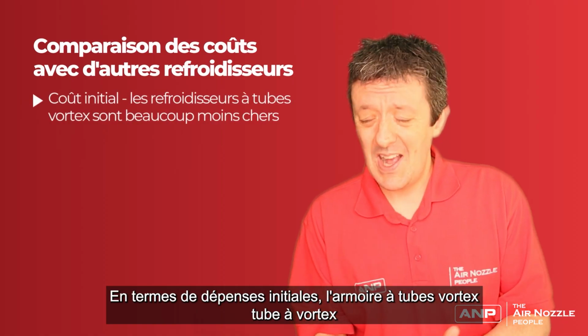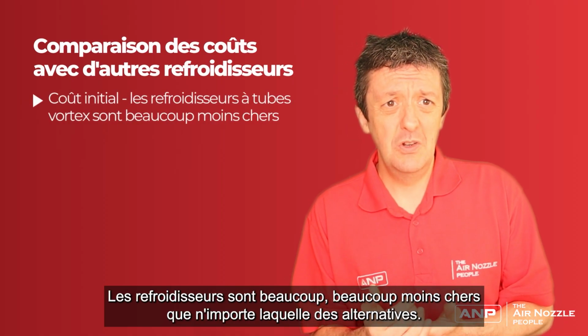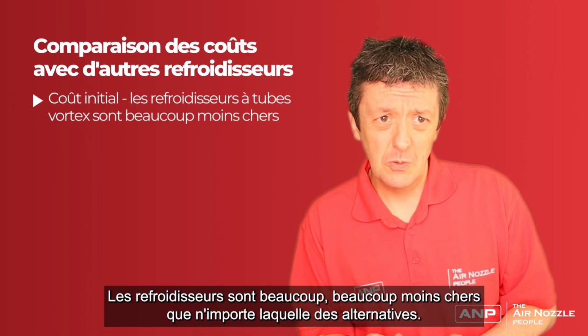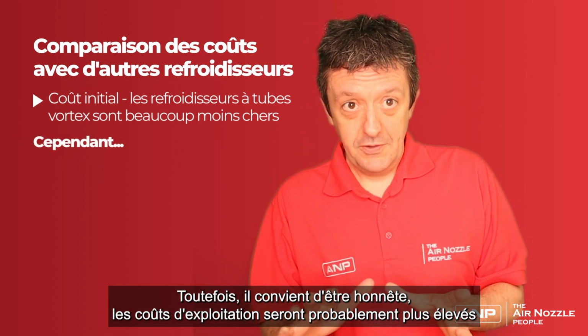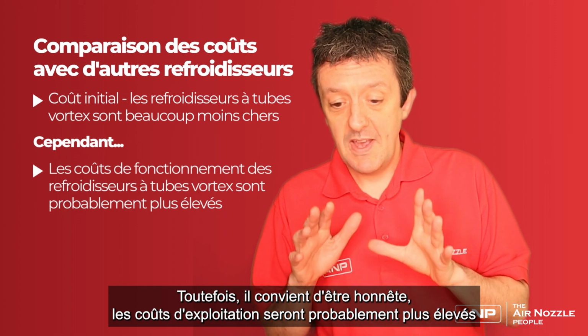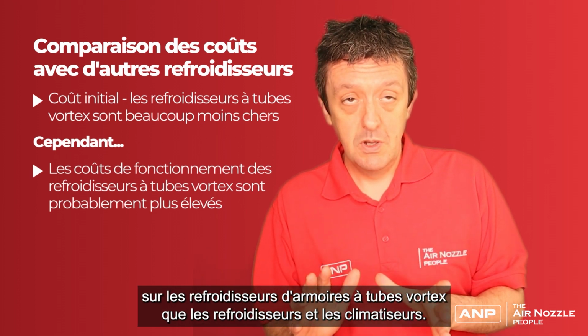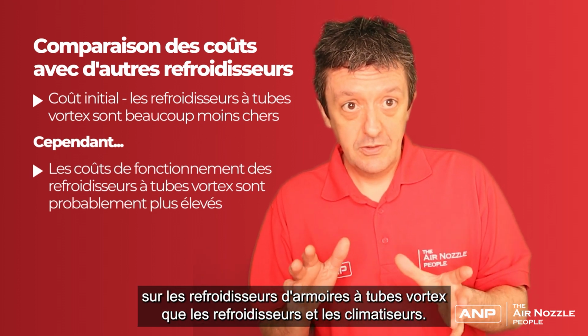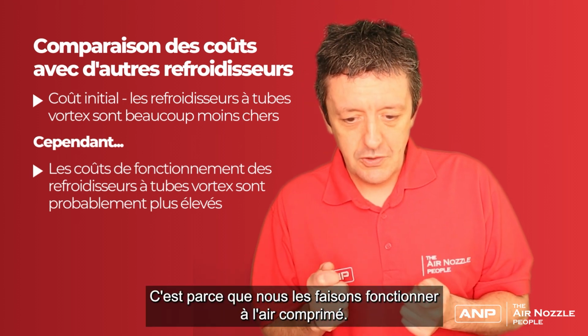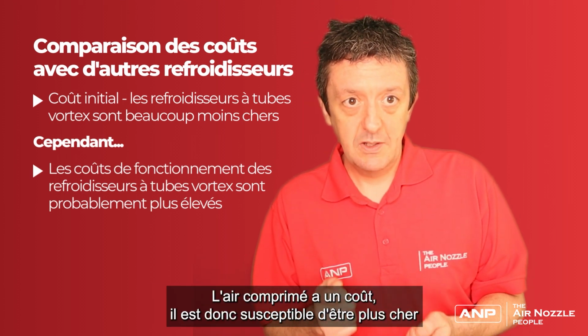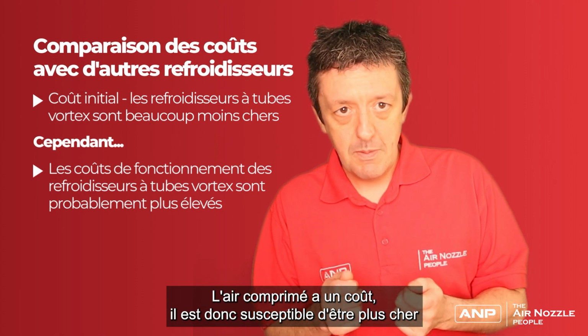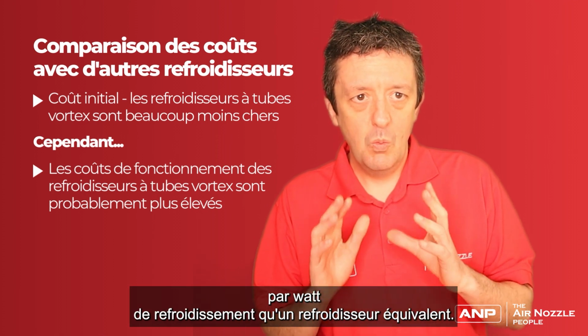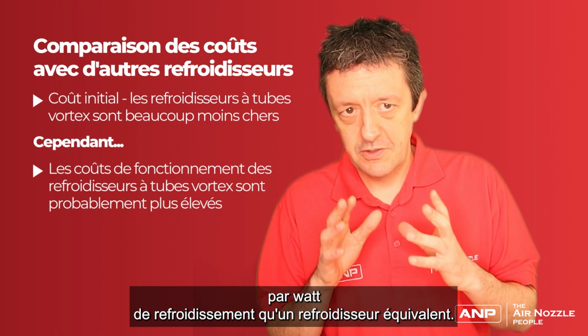So in terms of initial outlay, Vortex Tube cabinet coolers are much cheaper than any of the alternatives. However, we want to be honest here. The running costs will probably be higher on Vortex Tube powered cabinet coolers than chillers and aircon units. This is because we're running them on compressed air, and compressed air has a cost. So it's likely to be more expensive per watt of cooling than an equivalent chiller.